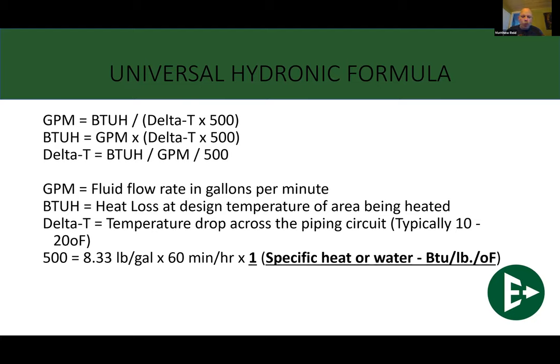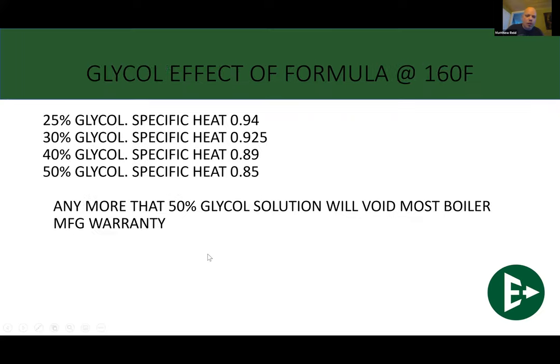A gallon of water weighs 8.33 pounds. We do everything in hours, variable BTUs per hour. So we times that by 60, and then we times that again by one. Now that number, that one is the specific heat of water. So that's where that comes from. If you have your calculators in front of you, do 8.33 times 60 times one, and you'll see it's, I think, 499.9 or something like that. And that's where that 500 comes from. But that 500 is not constant.